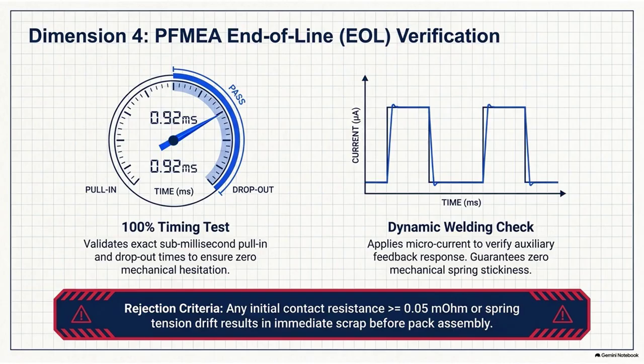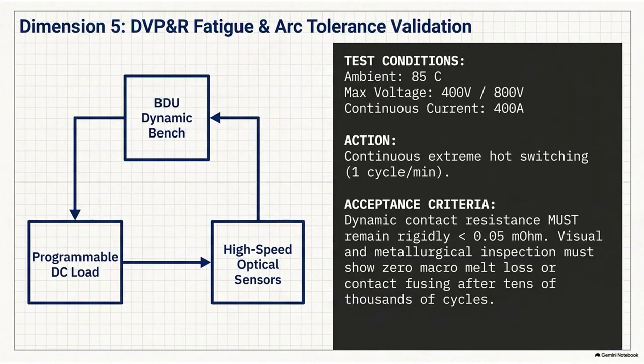The end-of-line testing for the high-voltage architecture is where the theoretical engineering meets physical reality. Every single assembled system, 100% of the production volume, no sampling, undergoes highly rigorous dynamic welding and mechanical timing checks. Mechanical timing checks, so they're essentially testing the stopwatch functions we talked about earlier. They are actively measuring the physical mechanical latency of the relay itself.